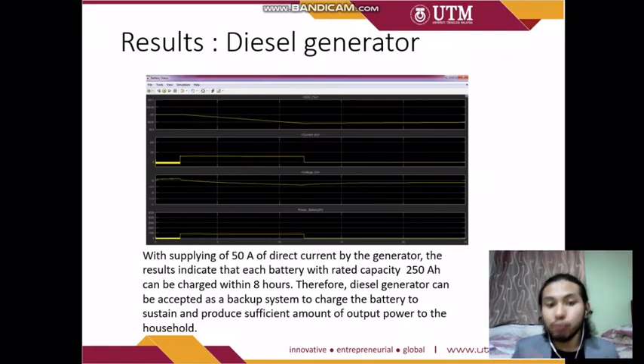With a supply of 50 ampere direct current from the generator, the result indicates that each battery with a rated capacity of 250 ampere-hour can be charged within 8 hours. Therefore, the diesel generator can be accepted as a backup system to charge the battery, sustaining sufficient power output to the household.